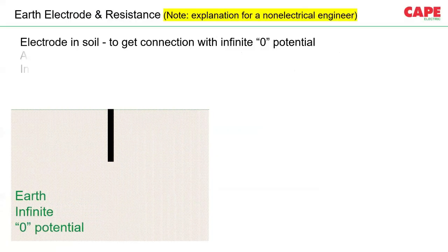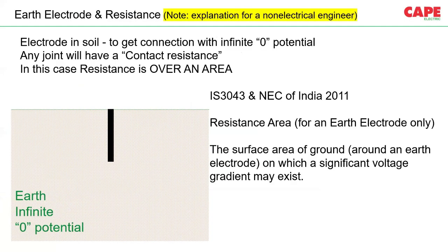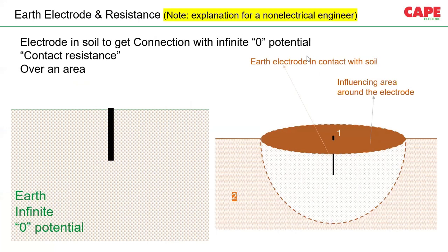So, resistance area is already very well established and explained in the respective standards. You have to refer to that. What this means is that this resistance is applied over an area in the soil. For example, here item number 1 is an earth electrode, 2 is the mother soil, and this hemisphere is the area which is influencing the resistance of the earth electrode. You can say that this is the influencing area of the electrode.